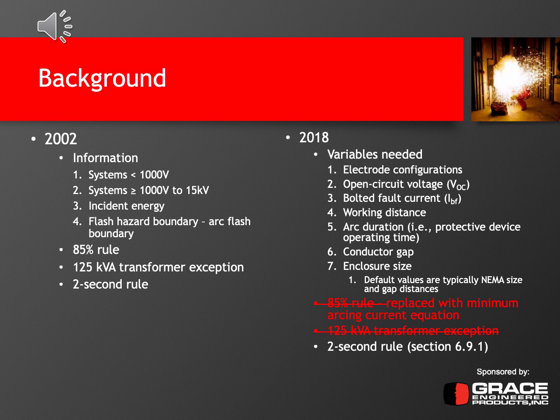The reason for that is that if you're right at the border on some protection settings, by dropping the arcing current by a fixed 15% down to 85%, you can see if you would then transition, say, from an instantaneous setting that would pick up the arcing fault to a short time, or from a short time to a long time. And that extra duration that's added based on the 85% rule could be significant when it comes to the overall available incident energy at that location.